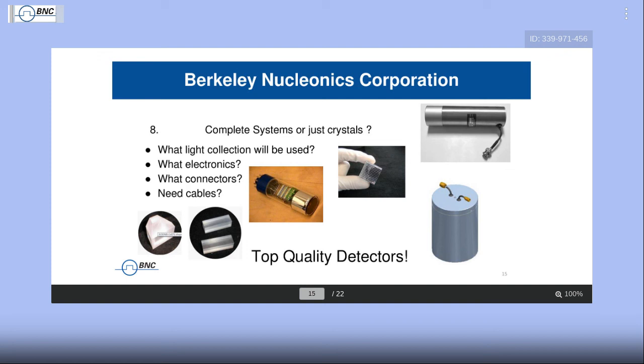Some are hygroscopic. Hygroscopic, we haven't covered that yet. Certain materials should not be exposed to ambient atmosphere. They will attract moisture. The moisture degrades the material itself. And so certain hygroscopic materials like sodium iodide, like cerium bromide, the lanthanums, most of the cesium are either fully hygroscopic or slightly. We will generally require, or at least advise, that these will be encased with, say, a glass window in an aluminum housing, and we will recommend the best way to deliver it to you.